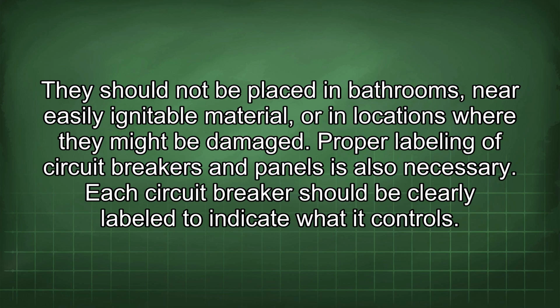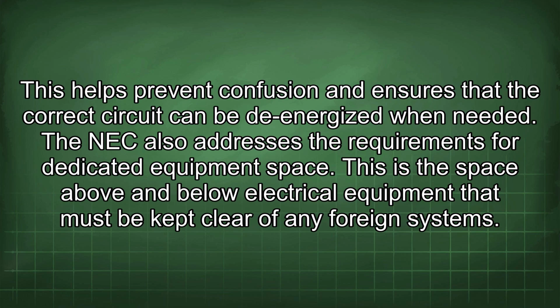Proper labeling of circuit breakers and panels is also necessary. Each circuit breaker should be clearly labeled to indicate what it controls. This helps prevent confusion and ensures that the correct circuit can be de-energized when needed. The NEC also addresses the requirements for dedicated equipment space. This is the space above and below electrical equipment that must be kept clear of any foreign systems.